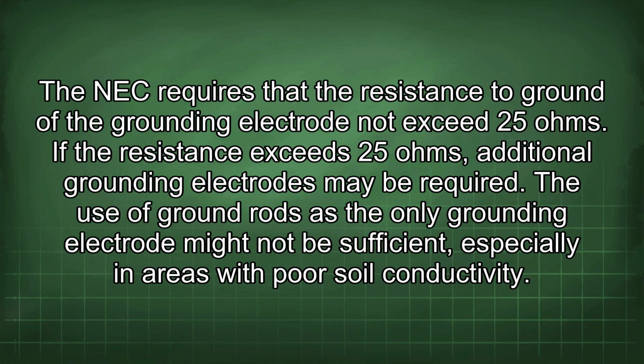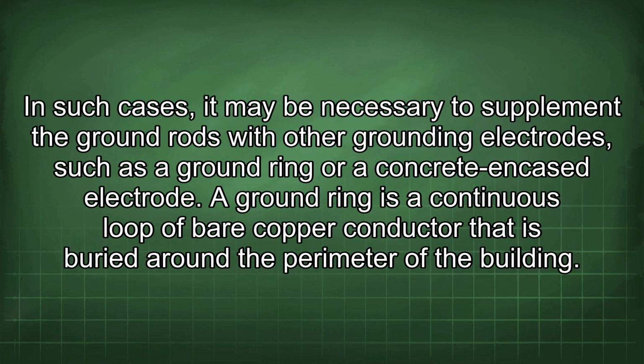The use of ground rods as the only grounding electrode might not be sufficient, especially in areas with poor soil conductivity. In such cases, it may be necessary to supplement the ground rods with other grounding electrodes, such as a ground ring or a concrete-encased electrode. A ground ring is a continuous loop of bare copper conductor that is buried around the perimeter of the building.